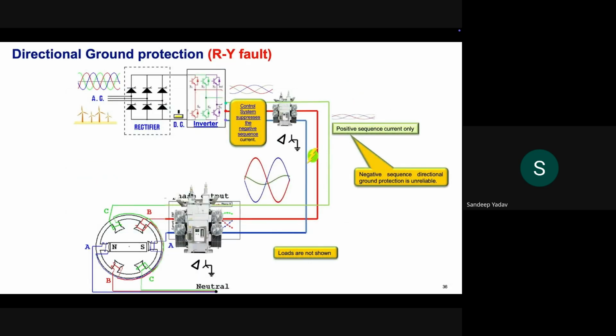So let's take the same example that we took a few slides back. For an R2Y fault, an R2Y phase-to-phase fault here, we know that the response from the conventional source will be 180-degree opposite currents. And because it is a phase-to-phase fault, the zero sequence will be very little, or may not be there at all, because there is no ground involved. So IR will be equal and opposite of IY.